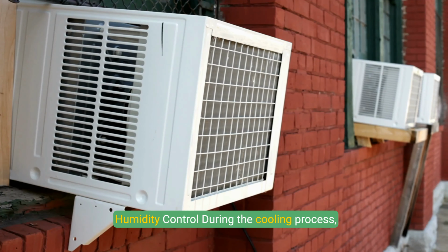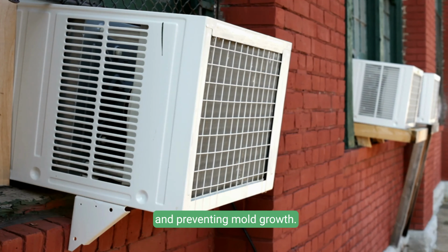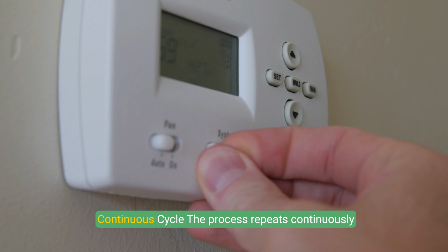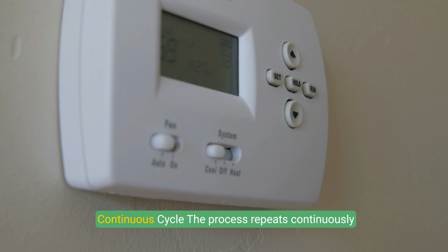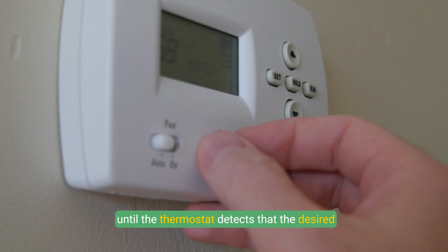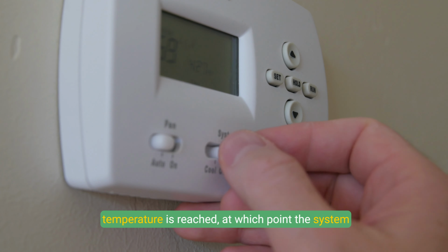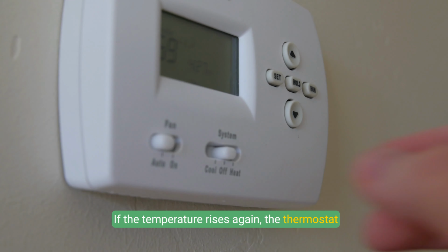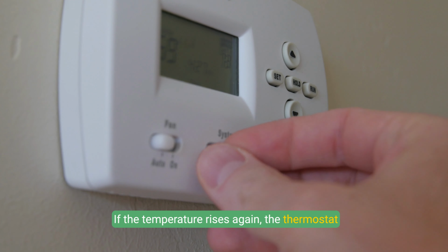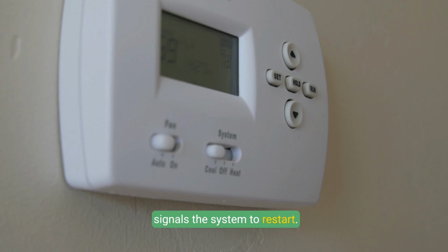7. Humidity control. During the cooling process, moisture in the air condenses on the evaporator coil and drains away. This reduces indoor humidity, enhancing comfort and preventing mold growth. 8. Continuous cycle. The process repeats continuously until the thermostat detects that the desired temperature is reached, at which point the system cycles off. If the temperature rises again, the thermostat signals the system to restart.